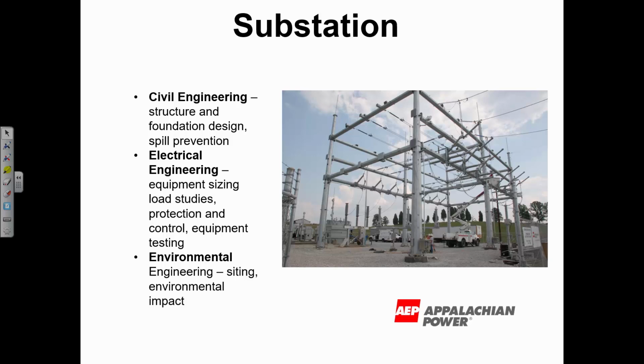You have to make sure the timing is proper and the zones of protection are set so you don't trip everything. If I've got a fault on one piece of line, I want just that piece tripping, not all the customers served from the rest being affected too.